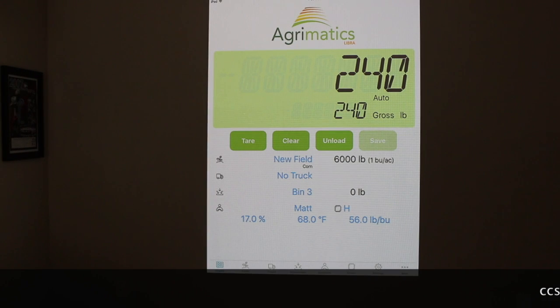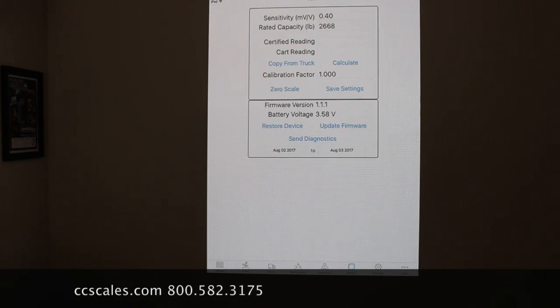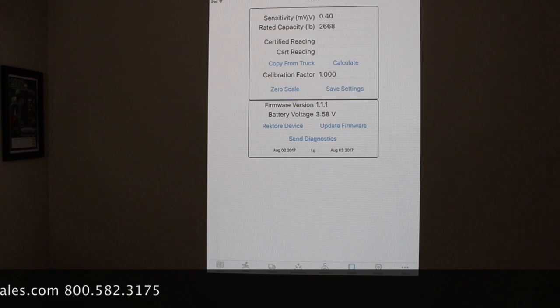Let's take a look at the most important thing, which is calibration. If you don't have calibration, you really can't have a reliable weight. So let's take a look at that calibration screen. To get there, you go to Device, which is the right of the Operators tab. So tap on Device, and then in the box at the very top, you'll see a sensitivity, and then a rated capacity, and then there's a cal factor.